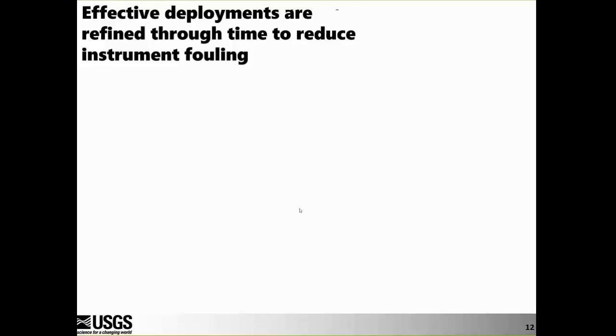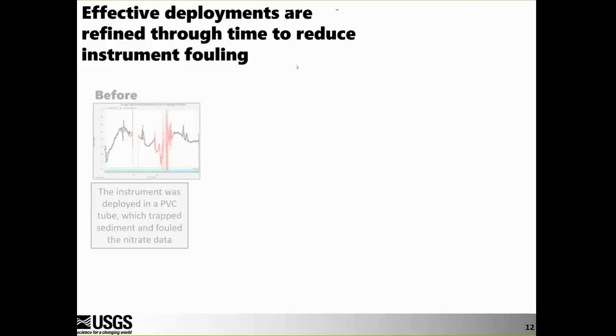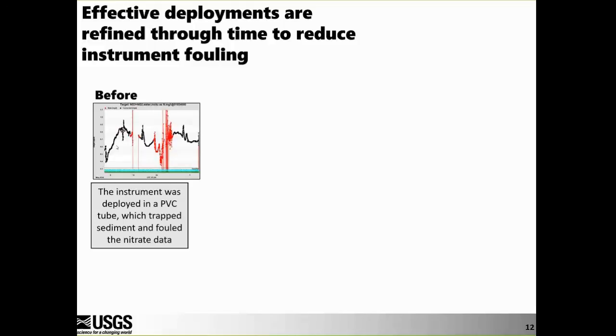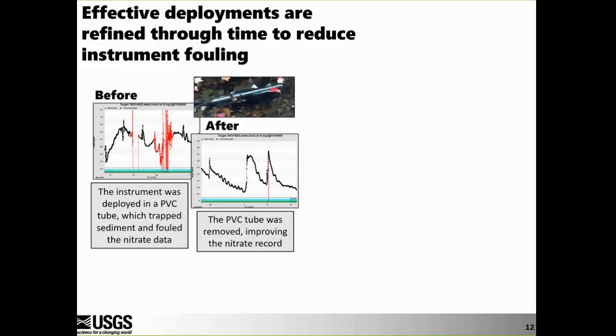Maybe one of the most important components of a water quality deployment is constant refinement through time — trial and error where modifications reduce instrument fouling. A time series graph of nitrate shows periods in red where data were deleted from the database because the instrument was fouled. Here, the instrument was deployed in a PVC tube that trapped a lot of sediment, consistently fouling the nitrate data. We removed the plastic case, which resulted in a much cleaner record.